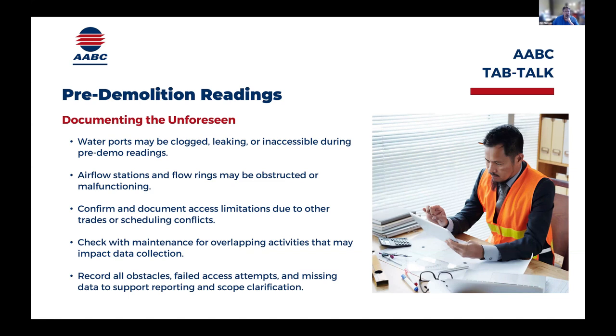Yeah, so going back to my article, this was 160 existing VAV box hot water coils to speak to the water balance inside. We found out very early that we were not going to get a reading off of every one of these combination circuit setters, auto flows, various companies, manufacturers. Early on, whether they were valved off, like Eric spoke of earlier, running into stuff like that, valved off, not getting flow through the port. If they're installed incorrectly, and this may have been 30 plus years ago, with the ports facing down, then obviously sediment is going to settle in there.